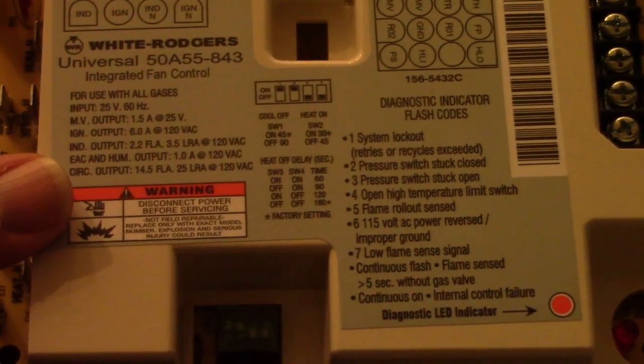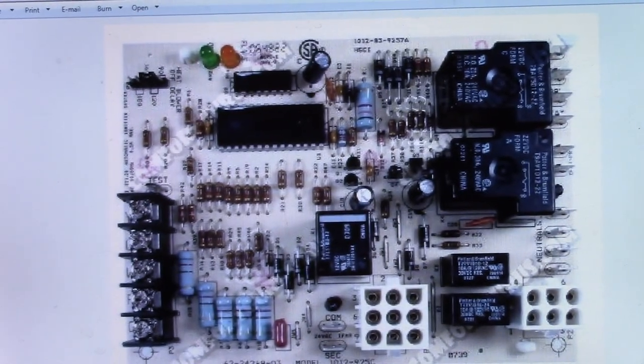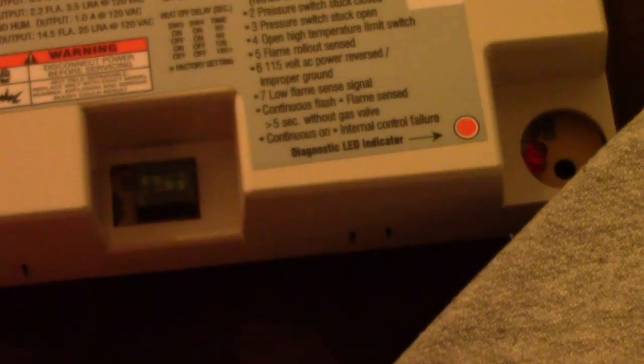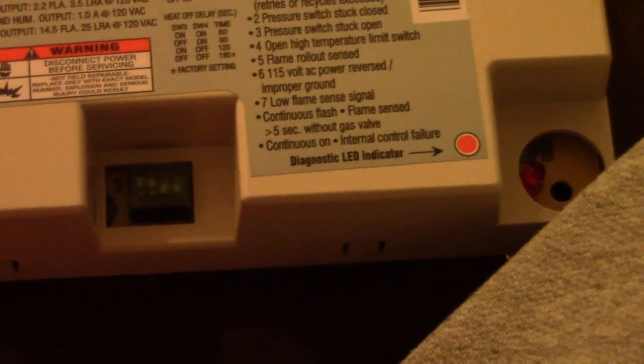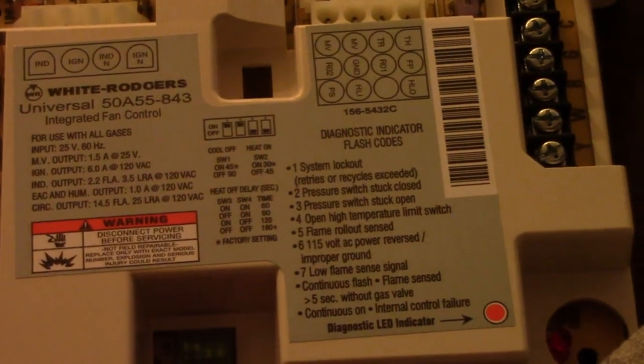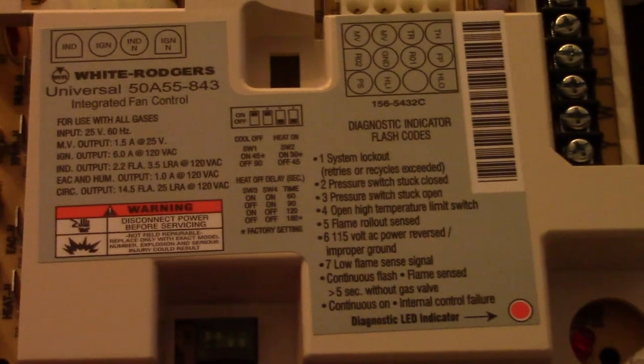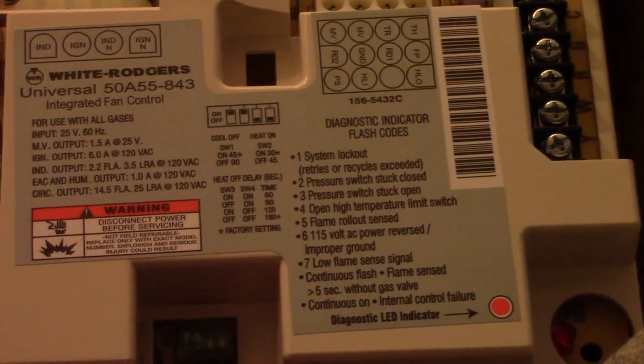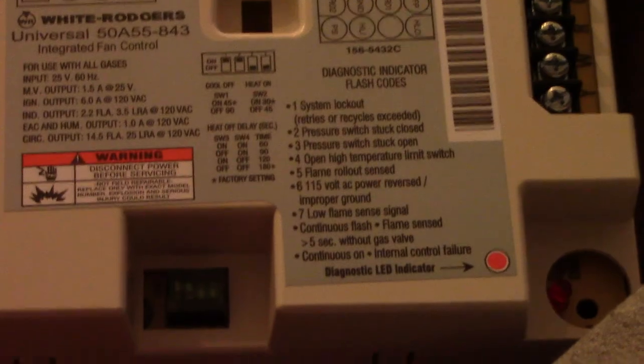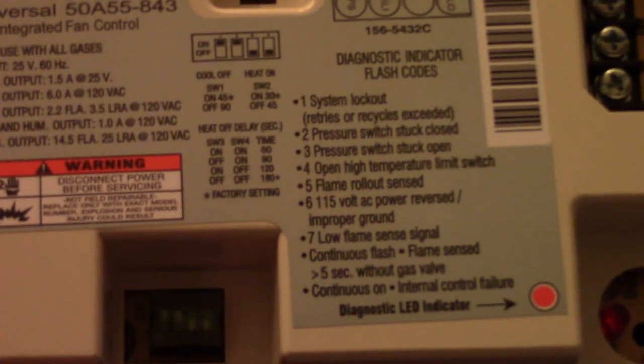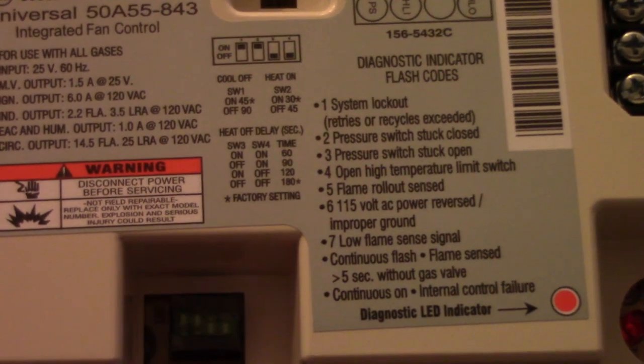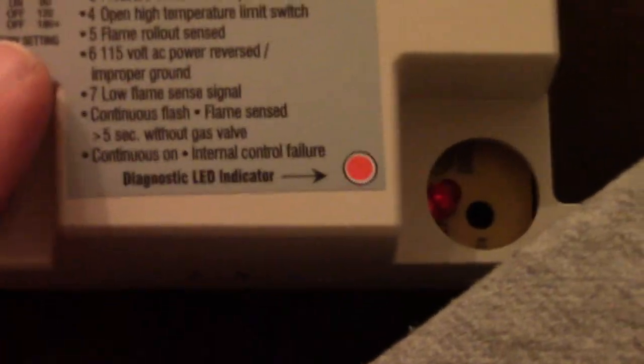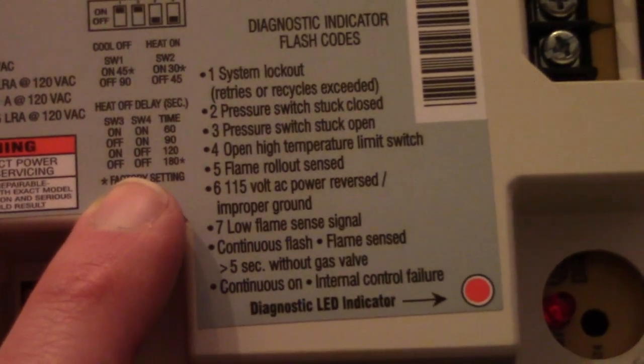I know Rheem furnaces will have a circuit board that looks similar to this, but it utilizes dip switches with no codes or anything to tell you. Meaning what you'll have to find is not the homeowner's manual, but the installer's manual for the furnace. A lot of times if you browse enough on the internet, you can find that, and it'll tell you how to program these switches. If you don't get it exactly right, you'll throw this off. So we're only using two switches here, switch 3 and 4 for that.